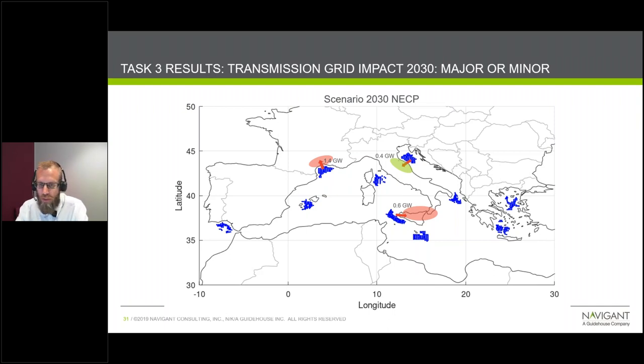The injection into Sicily, although not as large as the one into France, would likely mean major reinforcements being necessary, since the connection from Sicily to mainland Italy is a known weak point or bottleneck, and the grid down there is already quite congested.